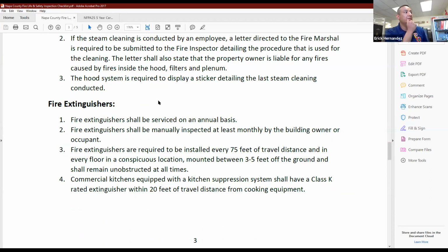So fire extinguishers. All commercial properties, fire extinguishers shall be serviced on an annual basis. And so they have a tag. There's two ways to do it. You can purchase new ones. If you are going to purchase one every year, make sure that before you buy it, you look at the proper date of manufacture. What I'm finding is lots of times people have a fire extinguisher that was manufactured in 2018 and hasn't been properly maintained. So before purchasing one, make sure you look at that date. Typically, you'll find it on the bottom of the fire extinguisher or on the actual tag. So make sure it's within the last year. So for now, we're 2021. I'm accepting 2020. If I see 2019, it would be a violation.